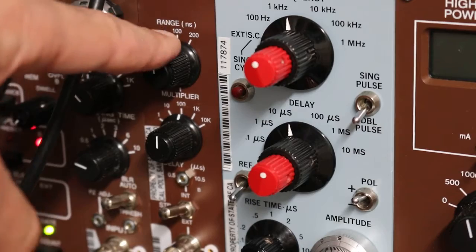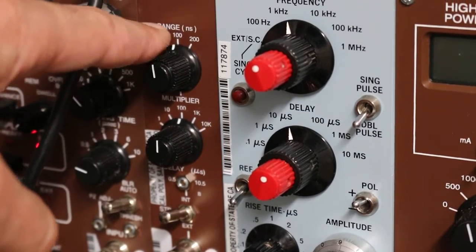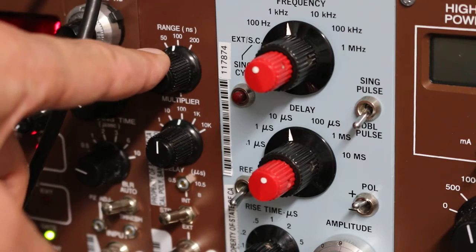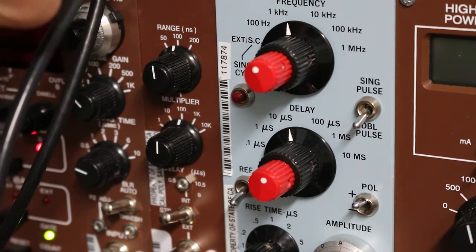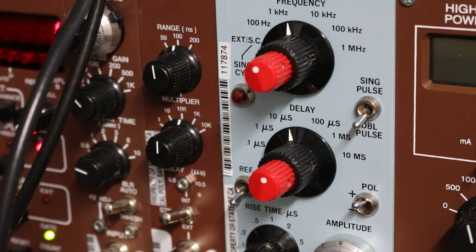Lastly, one of the settings on the TAC also is how long it should wait. You can see that there are 2 knobs here on the top. One is the range labeled in nanoseconds, and the other is a multiplier. This sets the maximum range that the TAC is going to wait for the end relative to the start before it'll internally stop and reset its own timing cycle.